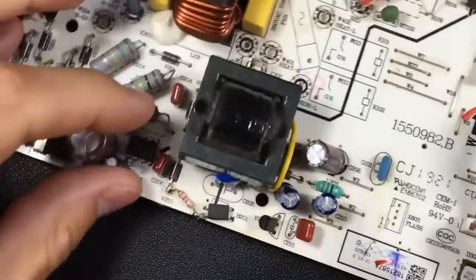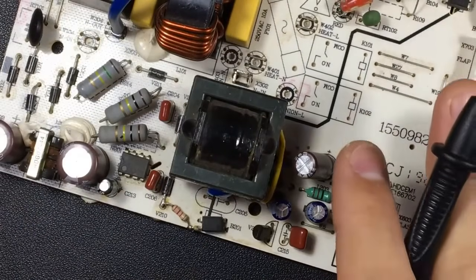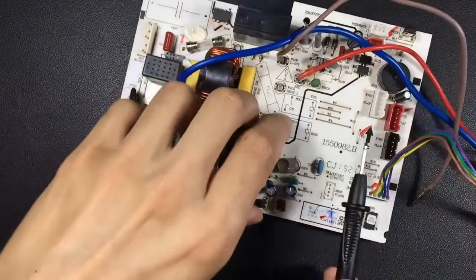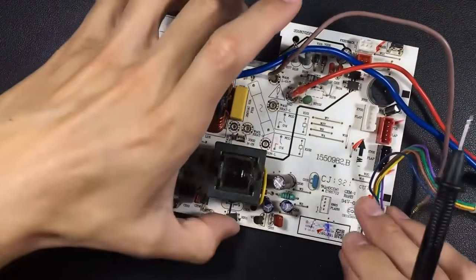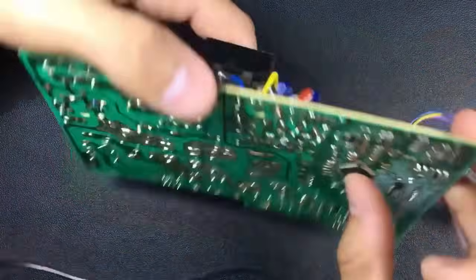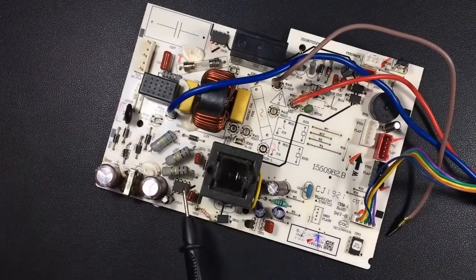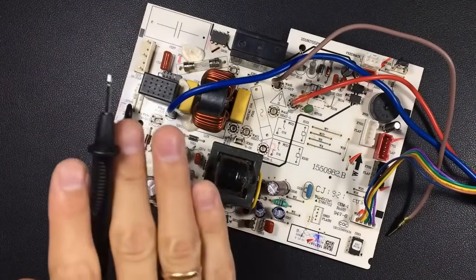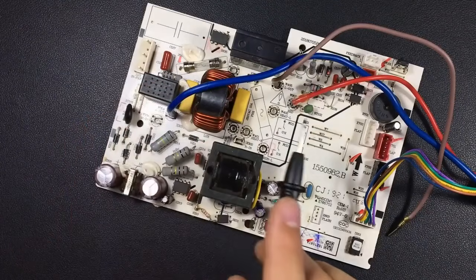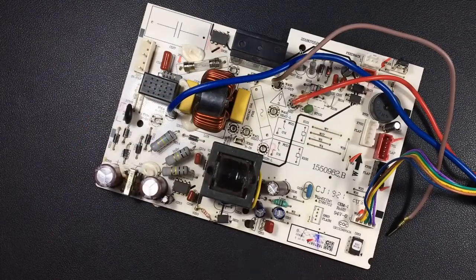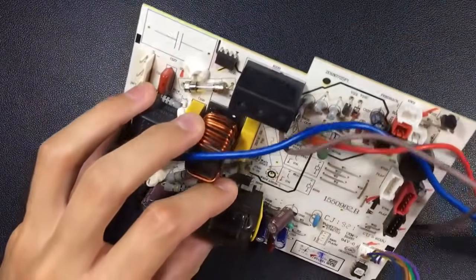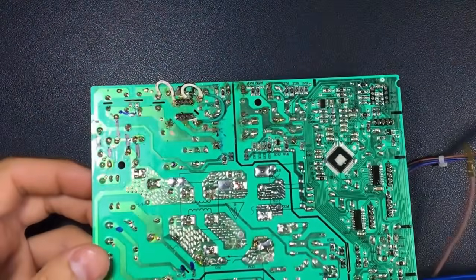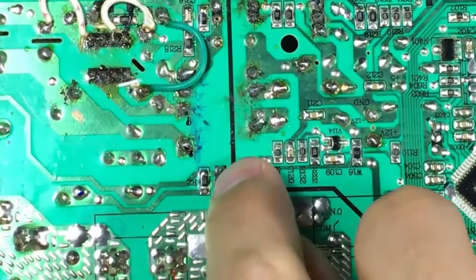When we have to inform the consumption from the microprocessor area, the consumption is informed from the delicate area, from where the microprocessor is, towards this side. And when we have to warn of the zero crossing from the side of the alternating voltage towards the microprocessor, the LED is placed precisely upside down. We have 2 optocouplers, but in the opposite position. If we wanted to measure it here, inside the board, we can also do it. We can test the LEDs at these points to see if they are in good condition.